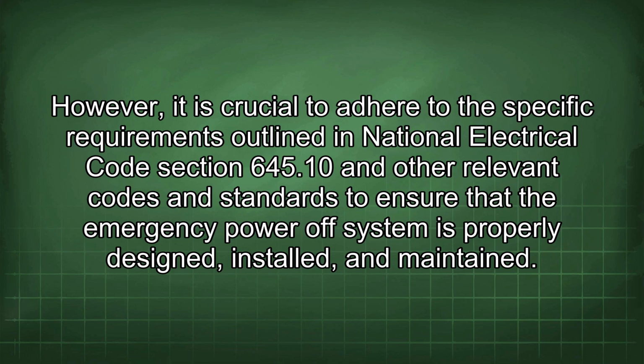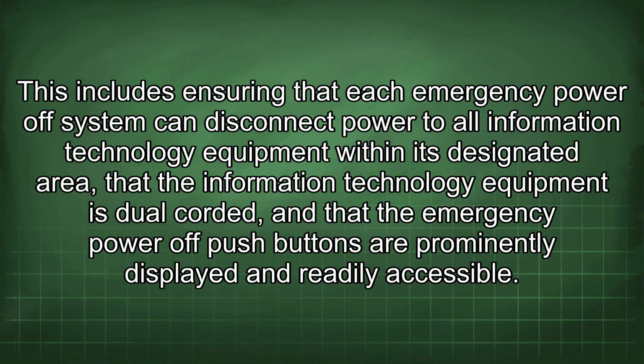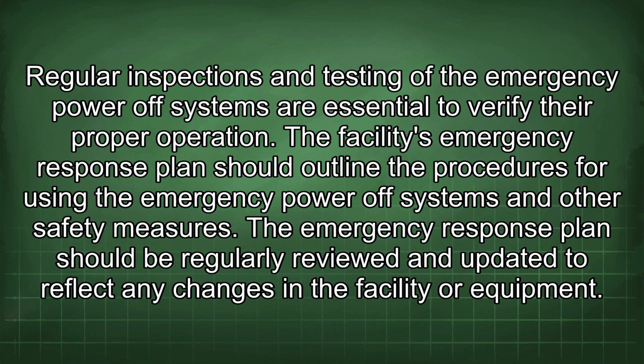However, it is crucial to adhere to the specific requirements outlined in National Electrical Code Section 645.10 and other relevant codes and standards to ensure that the emergency power-off system is properly designed, installed, and maintained. This includes ensuring that each emergency power-off system can disconnect power to all information technology equipment within its designated area, that the information technology equipment is dual-corded, and that the emergency power-off push buttons are prominently displayed and readily accessible. Regular inspections and testing of the emergency power-off systems are essential to verify their proper operation. The facility's emergency response plan should outline the procedures for using the emergency power-off systems and other safety measures. The emergency response plan should be regularly reviewed and updated to reflect any changes in the facility or equipment.